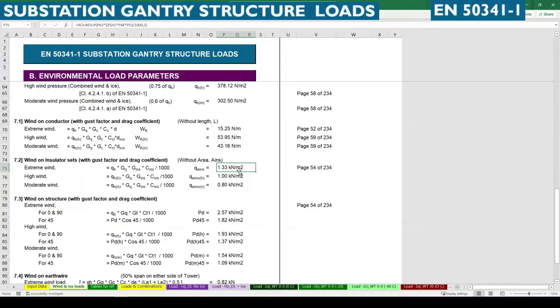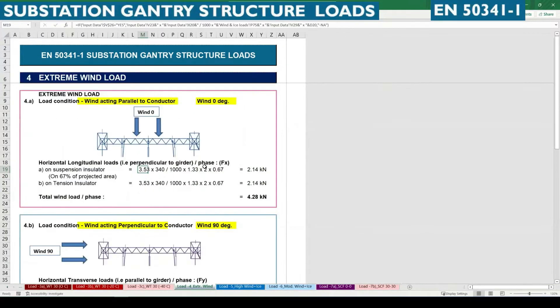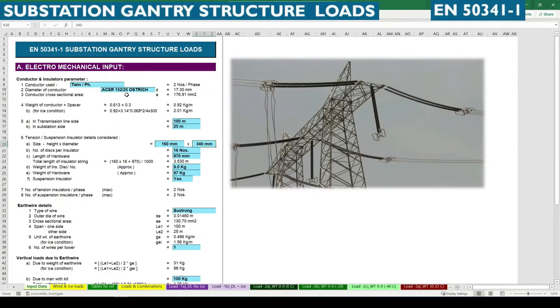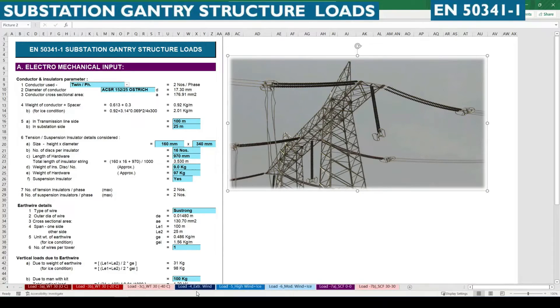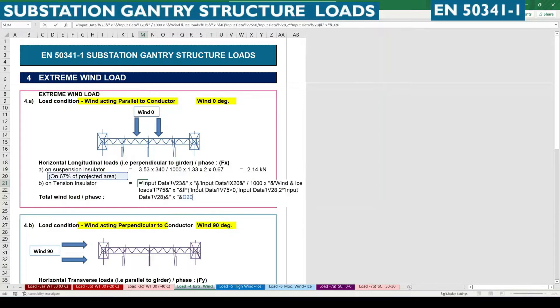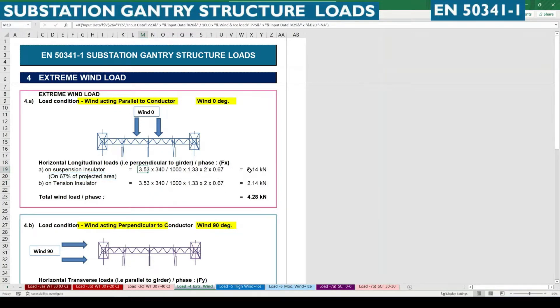We need to calculate this force in kilonewtons, so we multiply the area — which is diameter times length of the insulator. The factor of 2 means two numbers of insulator for suspension and tension insulator, as we are having a twin conductor. For a twin conductor there should be two tension insulators; a suspension insulator may be one. We calculate this and find the value is 2.14 kN.